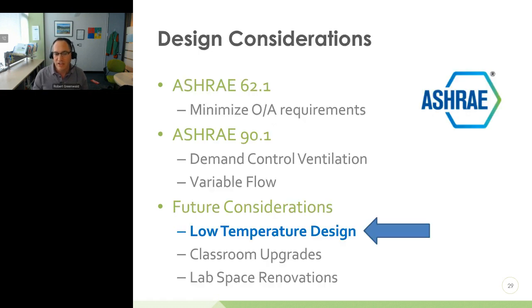We followed design considerations standard for what you'd expect in terms of ASHRAE 62.1 and 90.1. But what I want to focus on is the low temperature design. That's really enabled us to work on the next step, which is to allow for a low carbon heating plant retrofit, happening this summer.